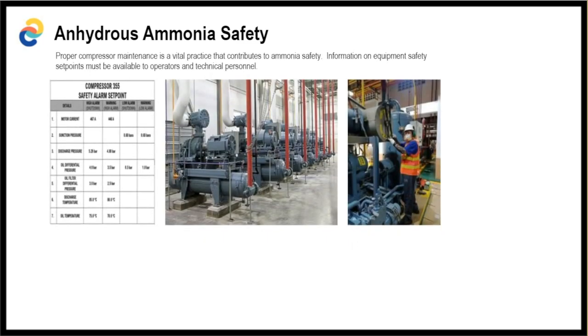For this slide, it shows the information of the equipment, the set points for the alarm, and also records of past faults should be kept. So it's sort of a history: should there be some activities done to an equipment, they should be recorded, and also what actions and what solutions have been made to it. Monitoring should be done to ensure that equipment in the plant is within the permissible operating conditions. So the settings.